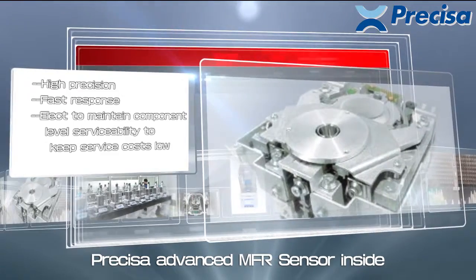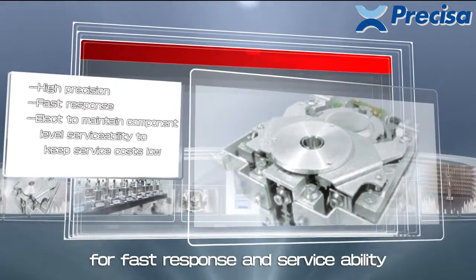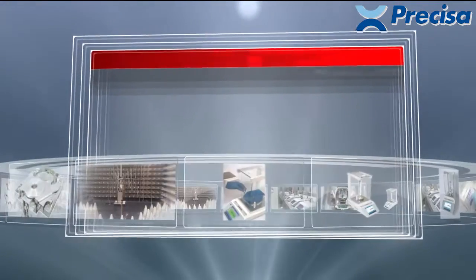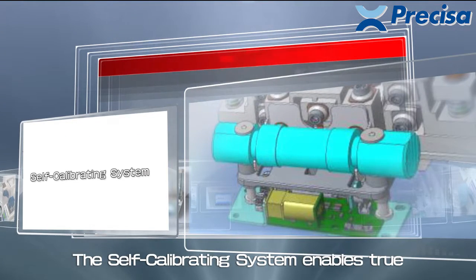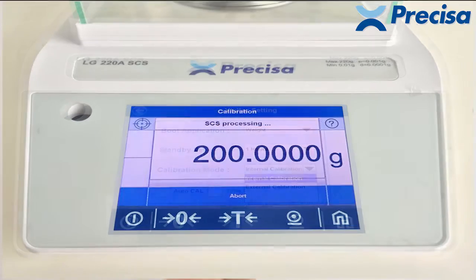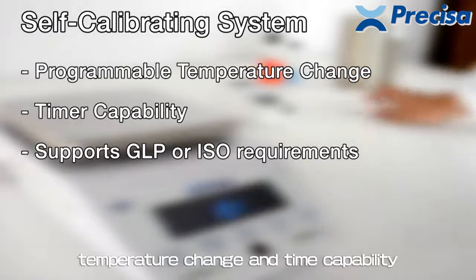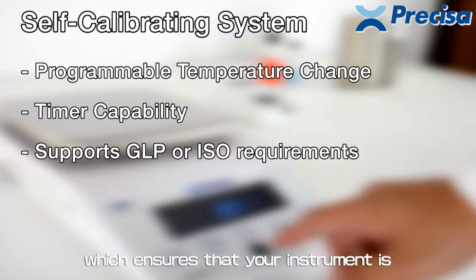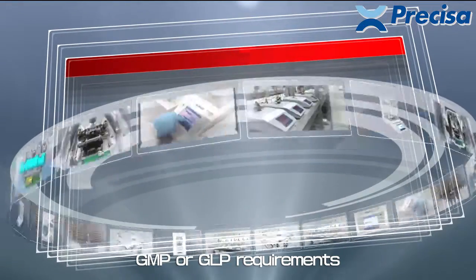Precisa's advanced MFR sensor ensures fast response and serviceability. The self-calibrating system enables true automated balance calibration, featuring programmable temperature change and timer capability, which ensures your instrument is always calibrated precisely to support GMP or GLP requirements.